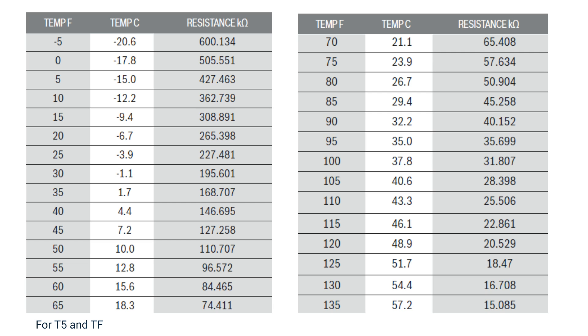Here you will see a resistance chart for the T5 and TF temperature sensors. These two sensors are 55,000 ohm thermistors. Measure the ambient temperature outside and correlate to the chart. If the ambient temperature reads 80 degrees, your reading should be 50,904. If any of your sensor readings are incorrect, replace the correlating sensor. If all readings are correct, then replace the faulty control board.